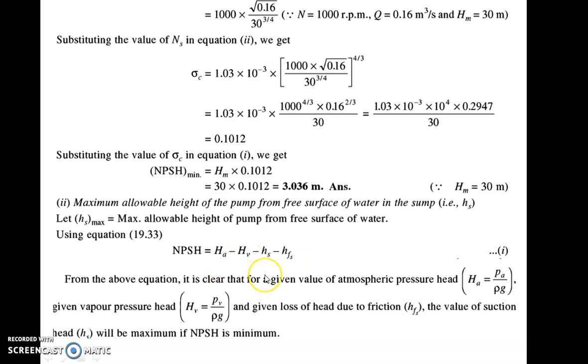So the maximum height of that pump will be coming as 6.652. You should not cross this height. If you cross this height, then your pump will have cavitation. So you can't keep your pump at a height of 7 meter from the ground level or from the sump level. You should take care of that. Such numericals may not come in the exam, but you should practice such numericals also.